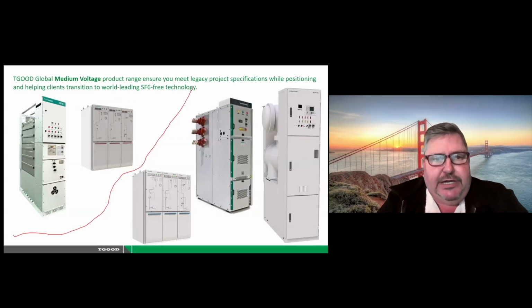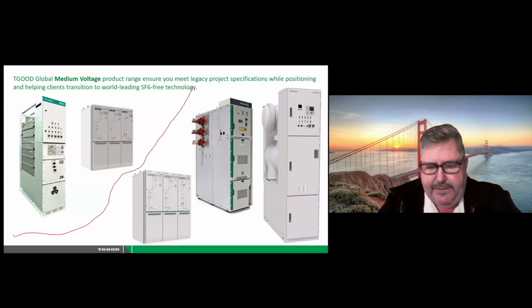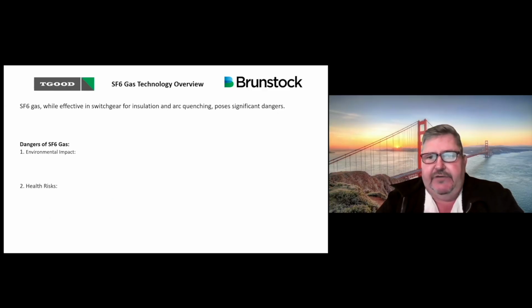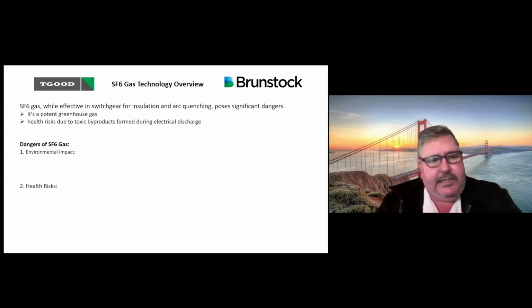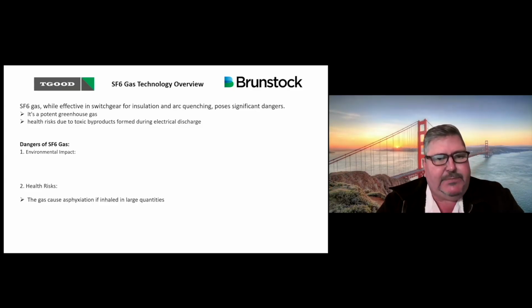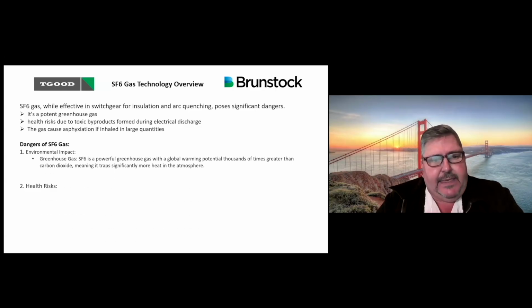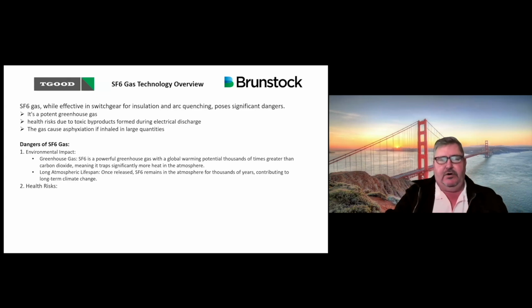From the traditional switchgear on the left-hand side, which is SF6 switchgear, TGOOD has now moved into a new range on the right-hand side, which is SF6-free switchgear. The reason is that there are significant dangers with SF6 gas, because when the arc is quenching, it creates byproducts that are harmful to the environment. It's a potent greenhouse gas, which is toxic and can cause asphyxiation as well. For the environmental impact, it is a global warming gas, which is very harmful, as we know, and it stays in the atmosphere for very long times.